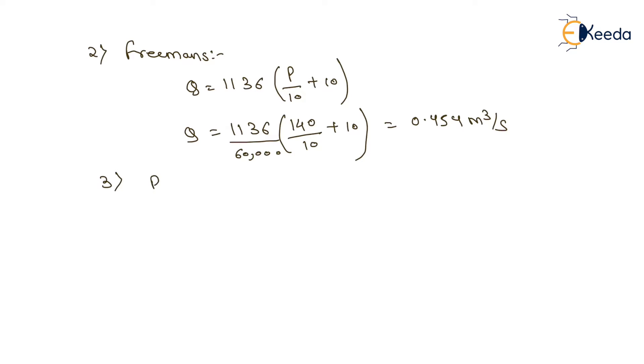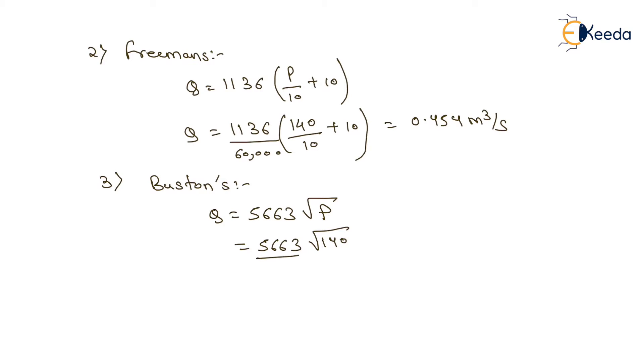The third one will be the Buston's formula. According to Buston's formula, Q equals 5663 root P. The value of P is 140, and we want the answer in meter cube per second, so we divide by 60,000. We get the answer as 1.116 meter cube per second as the amount of water per Buston's formula.